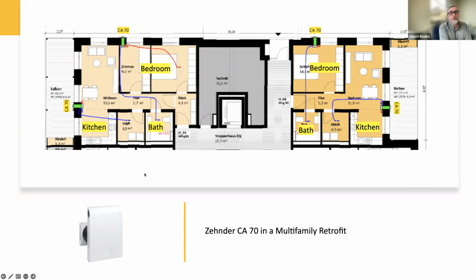And then above that, on the right-hand side of the schematic, we've got the really simple classic case where we put it in one location. We've got a little red arrow that's supplying into that bedroom constantly, 24/7. And then they've hooked up a duct with that second room adapter and run it over to the bathroom. So now there's no bath fan in the bath, because once we have continuous ventilation there, we don't need a bath fan. And so that thing's running all the time. These things run very, very quietly, and so they meet the typical requirements to be placed in a bedroom and not create too many noise hazards or things like that. So that's one way.